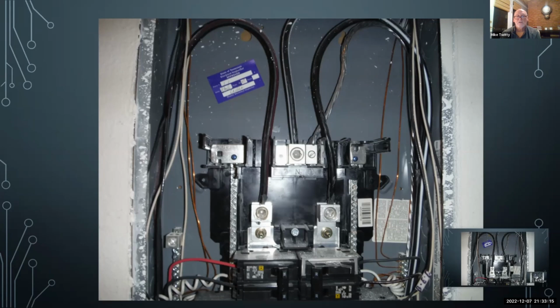Okay, like I say, this is a sub panel, 4-wire feed. See where they landed the equipment grounding feeder? It's right there with the neutral. It was supposed to be right there. That's where your equipment grounds. The equipment grounds were in the proper place. The neutrals were in the proper place, but there's no path back to the breaker that's feeding this panel because this should have gone here.